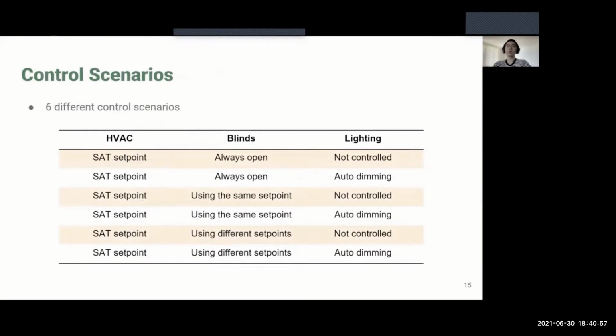To test how the joint control of building systems affects the performance of RL agents, we train all agents in 6 specific scenarios for controlling HVAC, blinds, and lighting, where we can assume the blinds are always open, or using the same set point for all blinds, or using different set points for each blind. The light can dim itself or not when the indoor brightness is high.